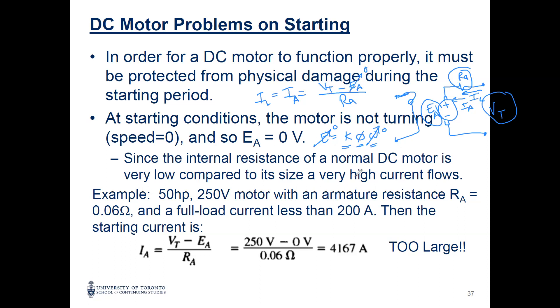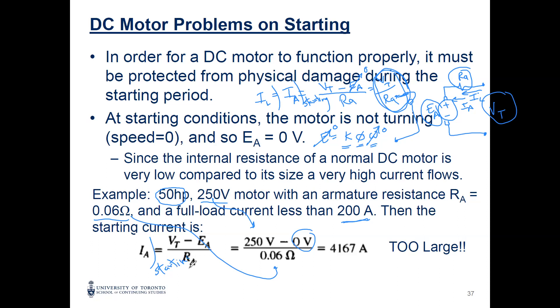With E_A equal to zero at startup, the starting current becomes V_T / R_A — which is extremely large. For example, with a 50-horsepower motor at 250 V with R_A = 0.06 Ω and rated current of 200 A, the starting current is 250 / 0.06 = over 4,000 amps. Compared to the rated 200 amps, this is extremely large.